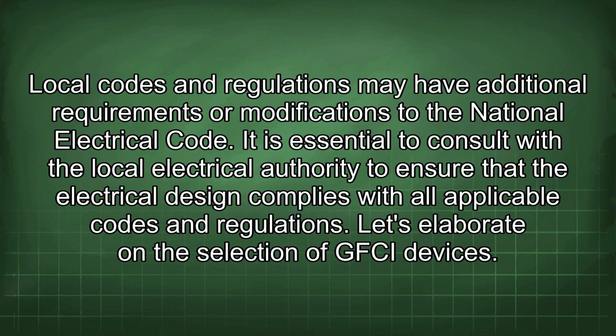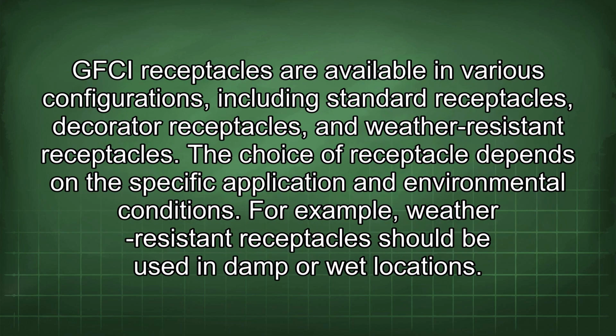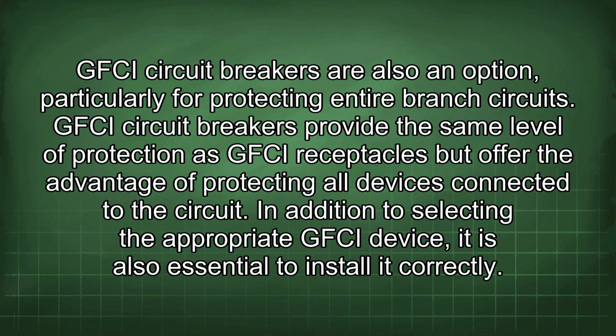Let's elaborate on the selection of GFCI devices. GFCI receptacles are available in various configurations, including standard receptacles, decorator receptacles, and weather-resistant receptacles. The choice of receptacle depends on the specific application and environmental conditions. For example, weather-resistant receptacles should be used in damp or wet locations. GFCI circuit breakers are also an option, particularly for protecting entire branch circuits. GFCI circuit breakers provide the same level of protection as GFCI receptacles but offer the advantage of protecting all devices connected to the circuit.